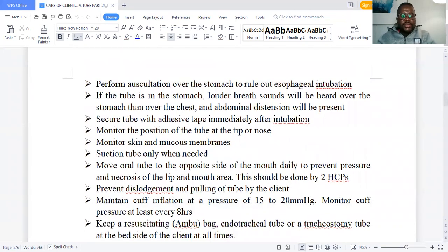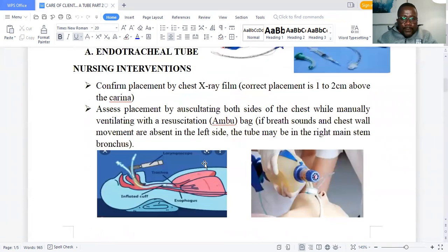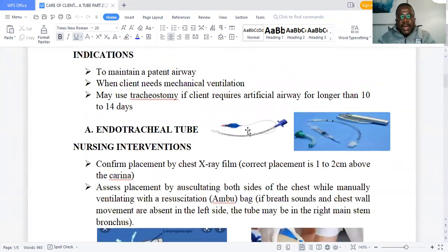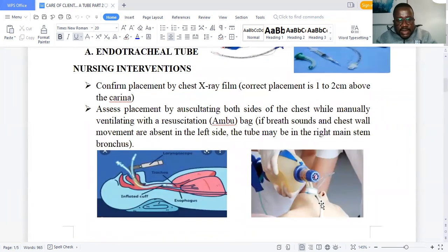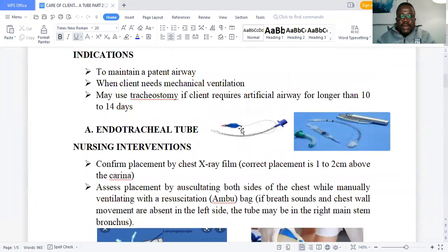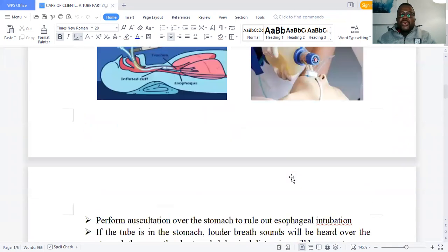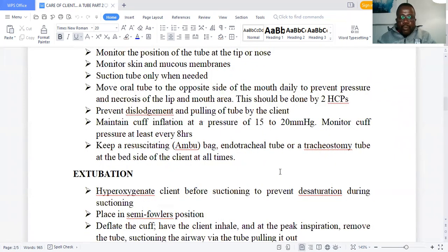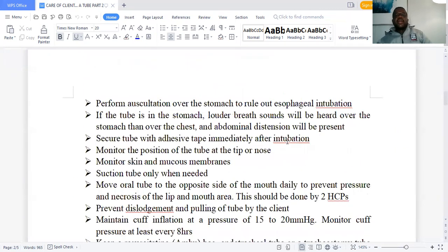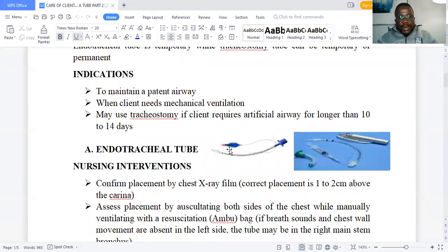This is very important. I told you this endotracheal tube has a balloon here. Now, when the tube is inserted, as you can see here, this balloon stays out. It is connected, goes inside. We want to maintain the cuff pressure, okay? You use a manometer to connect at this tip, and then you have to inflate it.